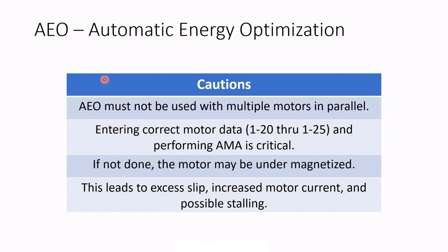Some things to be aware of: you cannot use the AEO function when you're running multiple motors in parallel on a single drive, such as a fan wall. That just won't work — use variable torque instead. It's very important to enter the correct motor data and perform the automatic motor adaptation in order for the AEO feature to accurately calculate how much it can reduce voltage. If these aren't done, the motor may be under-magnetized, resulting in excess slip, an increase in motor current, and the motor can possibly stall out entirely.